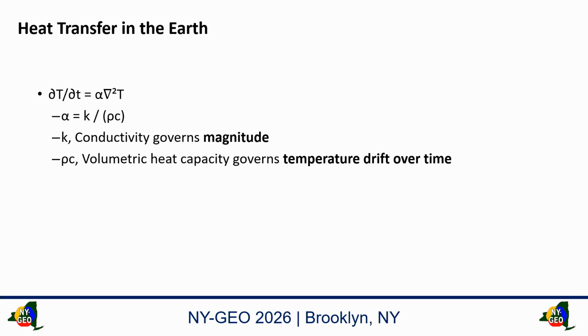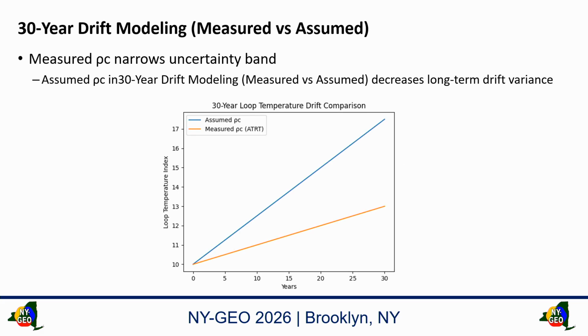Really, ASHRAE has three test standards that we use: line source, cylindrical, and numerical modeling. We do all three in that data set. So once we get there, we can directly tell you what that volumetric heat capacity on that earth locally is going to be. With that, we can start managing the thermal drift with time.